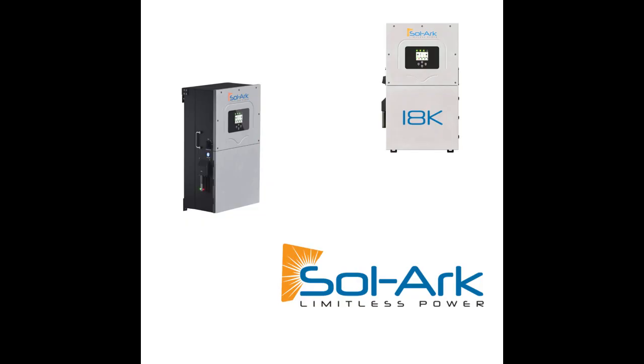Again, contrast to the 18K, that is a true 18 kilowatt output, both from PV and battery. So again, highlighting the differences, and we're just building off of the same architecture. And you kind of see that. So if you put an 18K and a 15K right next to each other, you're really not going to be able to tell. 18K is just a couple pounds heavier and about an inch taller, right? So we've gotten really good at really maximizing the power footprint for our inverters.